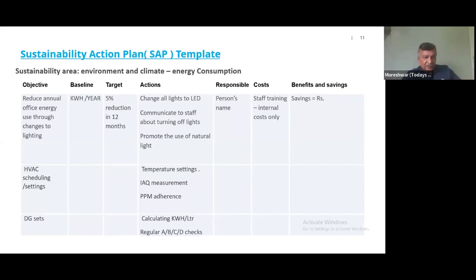Now PPM adherence, that is preventive maintenance adherence. People don't realize, they don't go for the A check or B check, saying 'I have not run even 250 hours, why should I go for A check?' Cummins says go for 250 hours. Okay, 250 hours not achieved, at least go for 500 hours. But people wait up to 1,200 hours.